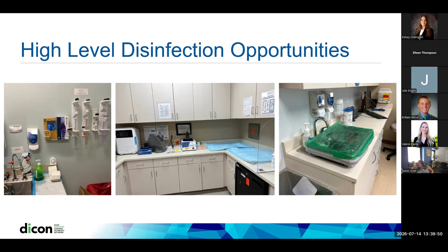In the middle picture, you can see it's not a great dirty to clean flow, where we have some instruments laid out to dry underneath those blue chux pads, but right over that is your specimen window that they're going to be pulling out and then doing point of care testing in the middle. And then on the right, we have clean flexible scopes that were pre-staged in transport containers and distributed to all of the rooms in advance of what they perceived to be a quite busy clinic day. And in this case, they even put that clean scope right on top of the hand washing sink.